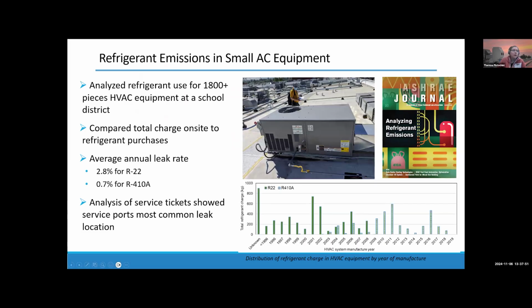So how did we get here? We were contracted to do a study on refrigerant leaks in packaged HVAC systems. We went out to a school district a number of years ago, in 2020 and 2021, and analyzed the refrigerant use at that school district in 1,800 pieces of equipment. We went through all the refrigerant purchases and looked at all of their HVAC inventory, and we calculated the leak rate as a percentage of the total refrigerant on site. We came up with about 3% for R22 and less than 1% for R410A.